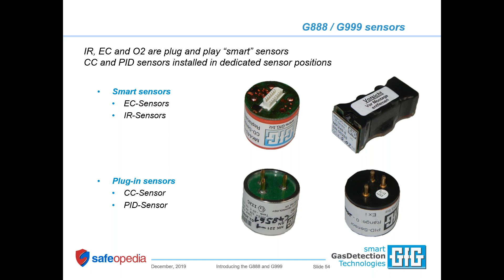We measure it directly with a substance-specific hydrogen sensor, and for CO and H2S measurement, we deliberately use sensors that do not respond to hydrogen. So we really do a better job on this than I think is being done with products that I see being sold by some of our competitors. The electrochemical sensors and the IR sensors are plug-and-play smart sensors. The catalytic LEL sensor and the PID are plug-in sensors where the board needs to have a dedicated position, and that's what drives those issues with the different board variations for the 999.